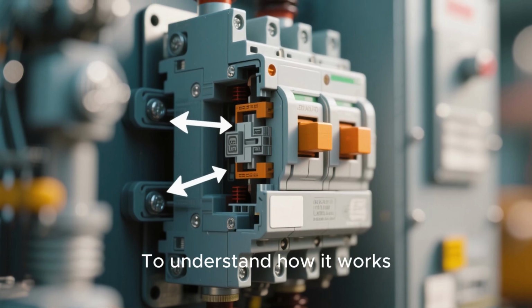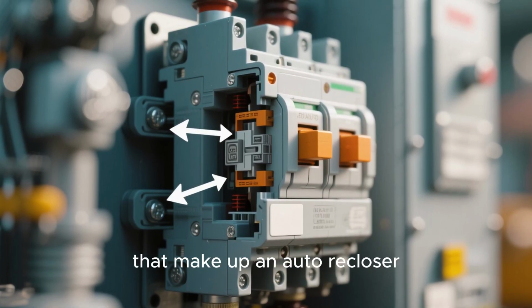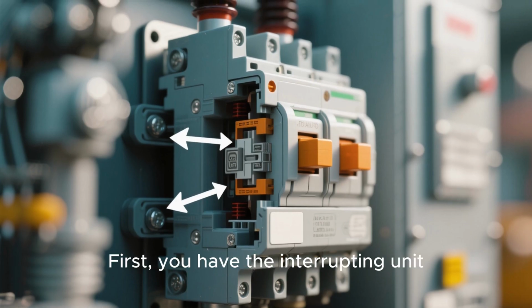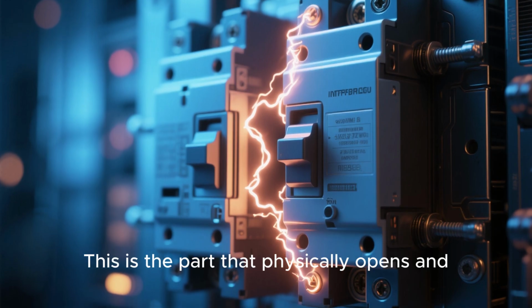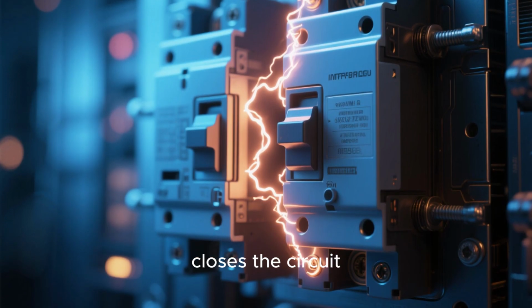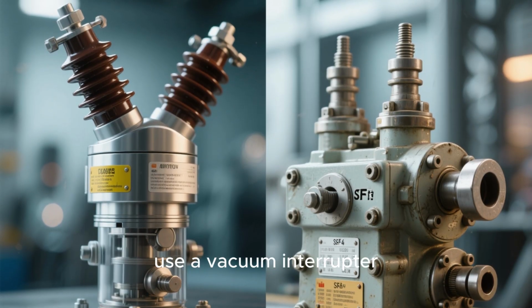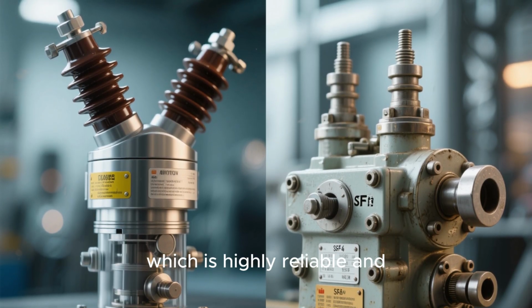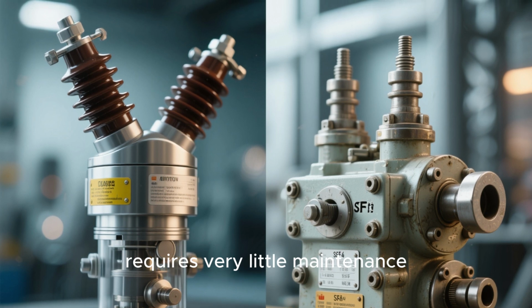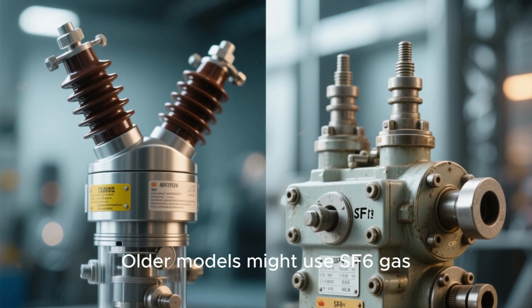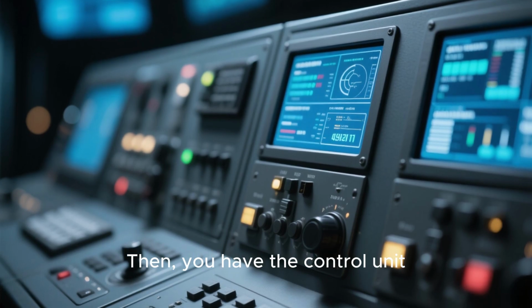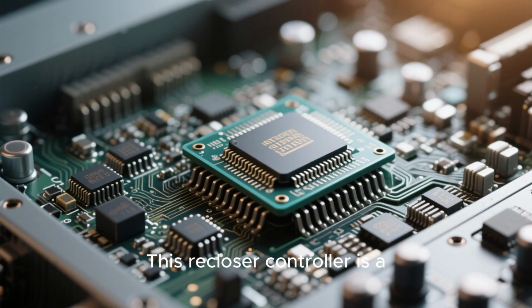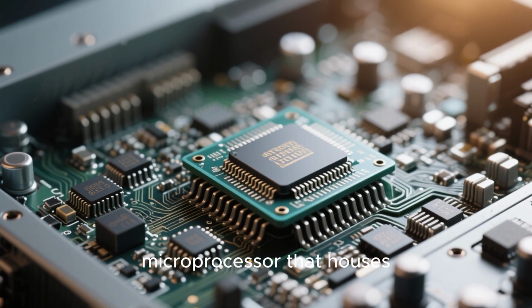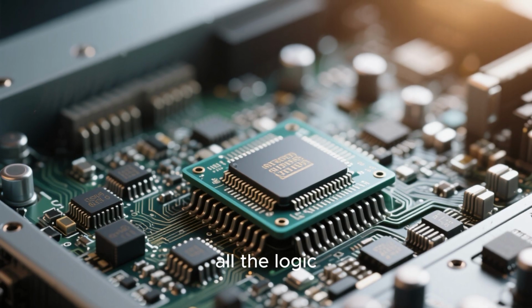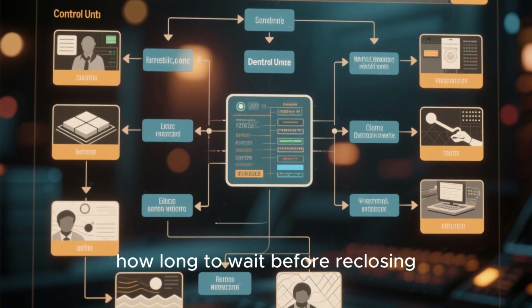To understand how it works, let's look at the main components that make up an auto recloser. First, you have the interrupting unit. This is the part that physically opens and closes the circuit. Most modern reclosers use a vacuum interrupter, which is highly reliable and requires very little maintenance. Older models might use SF6 gas. Then, you have the control unit, which is the brain of the system. This recloser controller is a sophisticated microprocessor that houses all the logic. It decides when to trip, how long to wait before reclosing, and how many times to try.